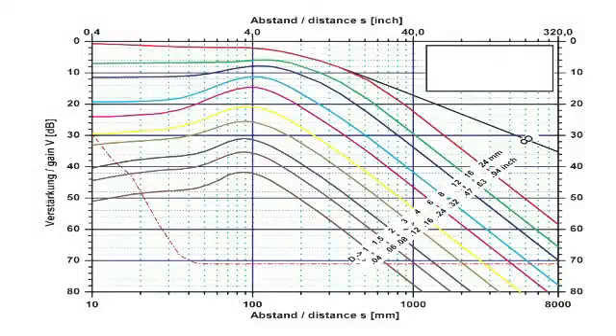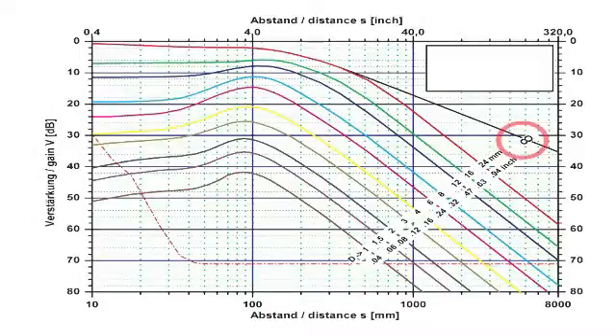Within the DGS diagram, the distance dependency of the echo amplitudes from large reflectors, in this case the back wall, and small reflectors, flat bottom holes having different diameters, is shown graphically.